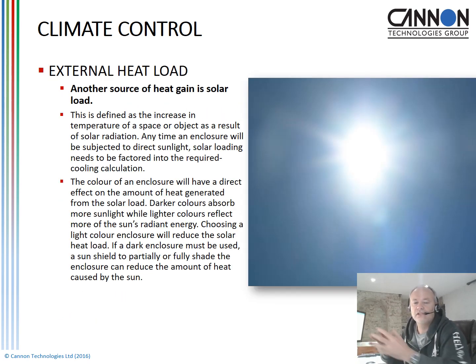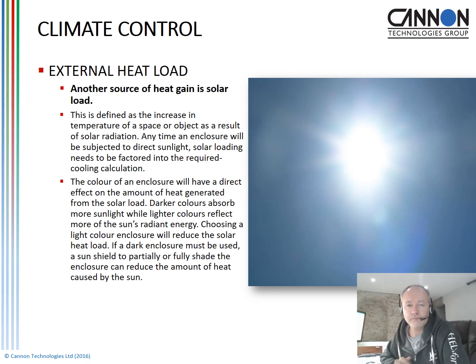So looking at the external heat load, this can be a solar heat gain. This is defined really as an increase in temperature of a space or an object as a result of solar radiation, heat from the sun. Anytime an enclosure will be subject to direct sunlight or solar loading, it needs to be factored into that actual cooling calculation, obviously that heat from the sun.